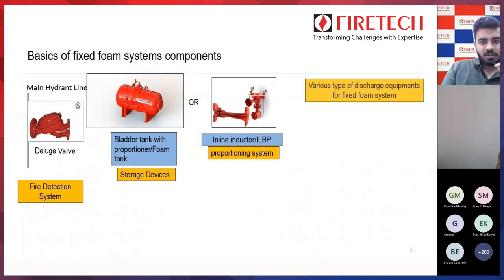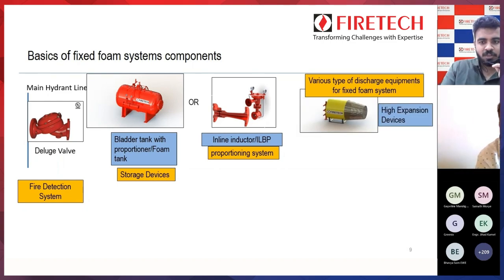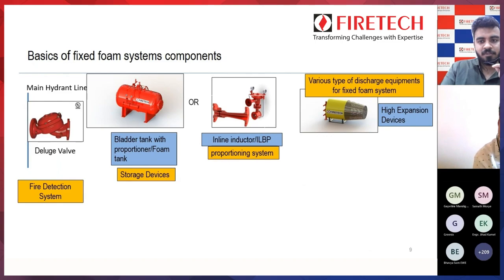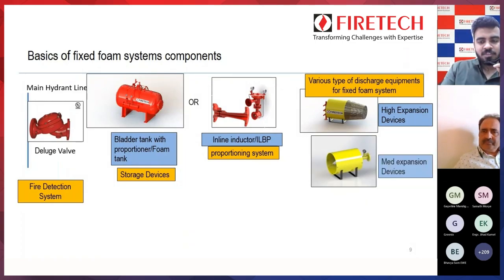Fourth is the discharge devices. You need to use various types of discharge devices for the fixed foam system. The first is high expansion foam generators, which are basically used in LPG fires — for spill fires. High expansion foam generators are used there. Second is the MEFG, which is used in the storage tank for dike protection.